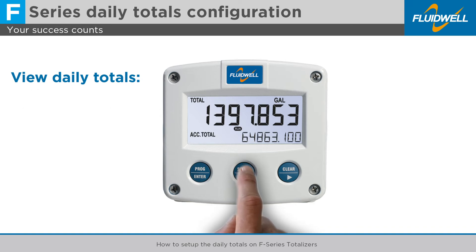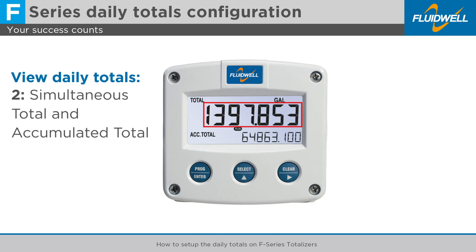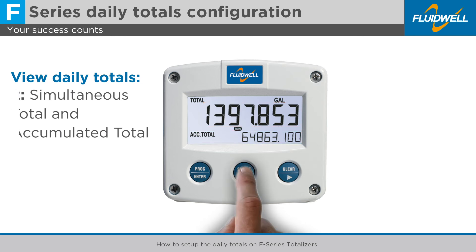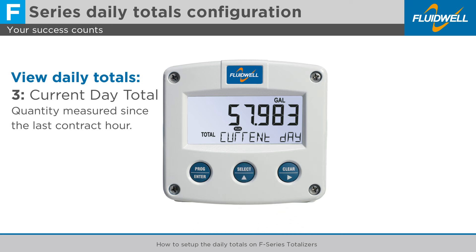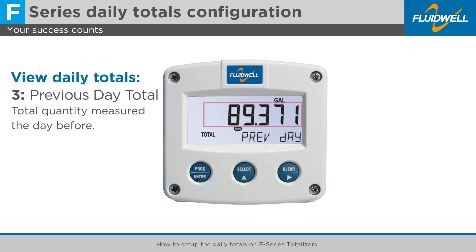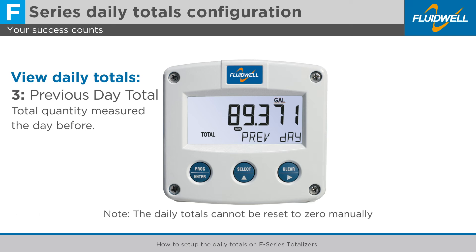Press select to display the next screen — it shows total and accumulated total simultaneously. Press select again to display the next screen. It shows the current day total, or daily total, which is the quantity measured since the last contract hour. Press select to display the next screen. It shows the previous day total, which is the total quantity measured the day before. They all share the same measuring unit for total at the top of the screen. Note that the daily totals cannot be reset to zero manually.